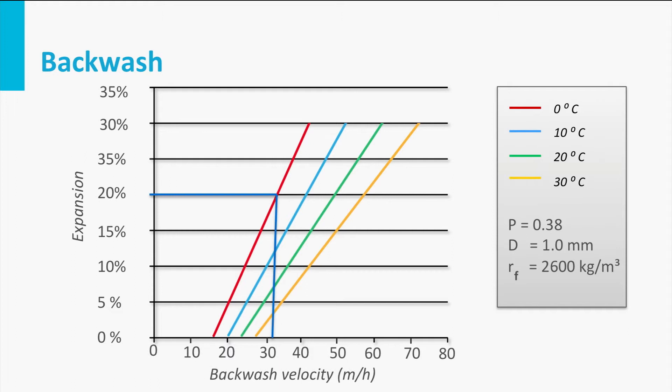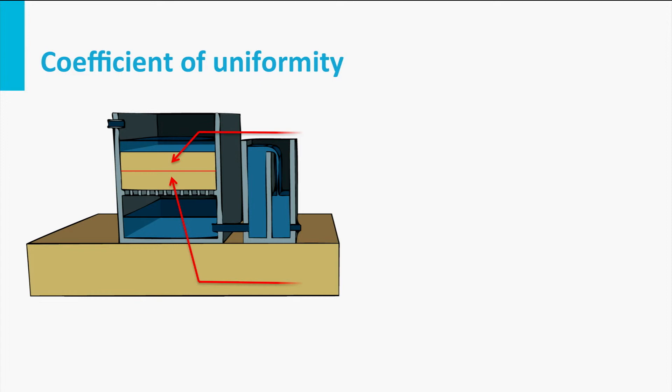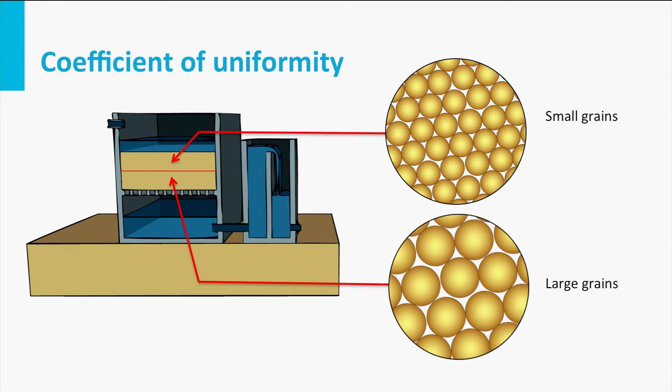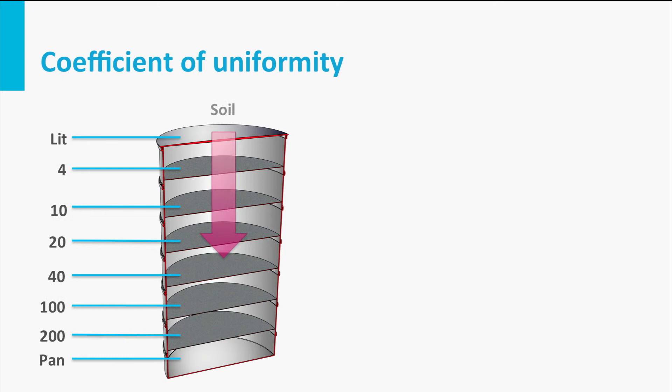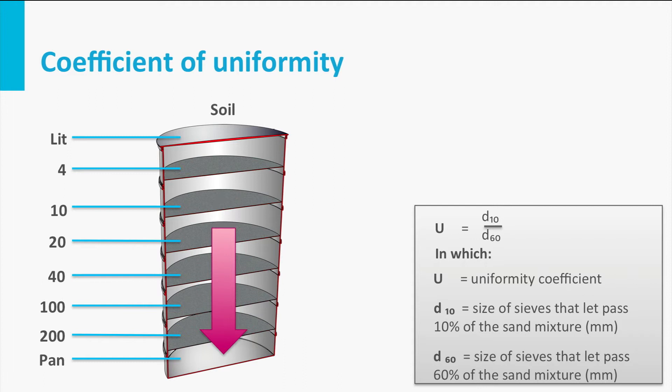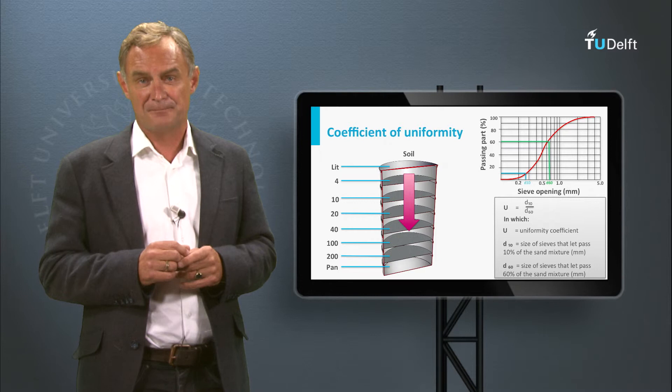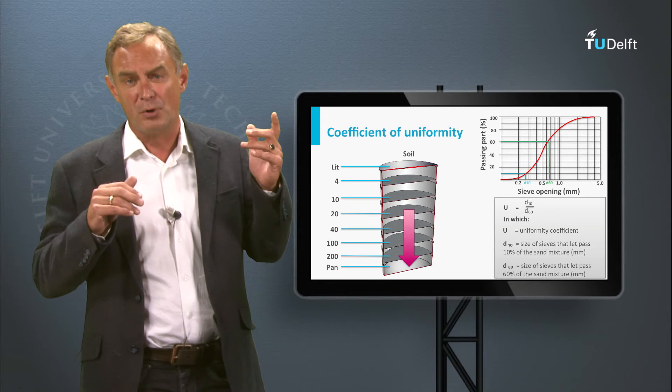To avoid that during backwashing the small grains float to the top and the larger grains settle to the bottom, the filtering material must be uniform. This can be obtained by sieving the sand and calculating the coefficient of uniformity U, determined by the quotient of the 60th and 10th percentile grain sizes. The coefficient of uniformity should maximally be between 1.3 and 1.5.